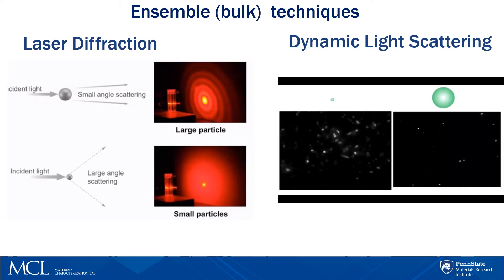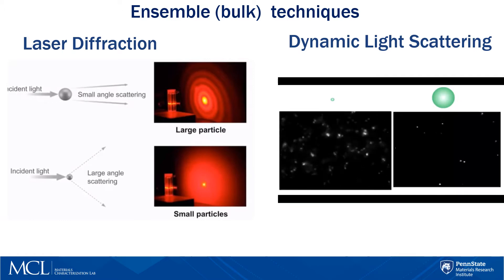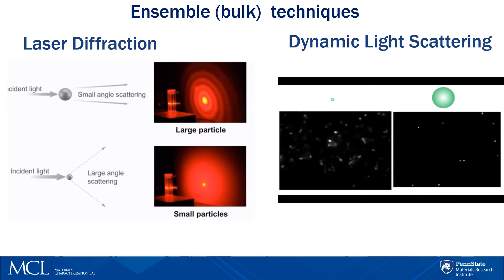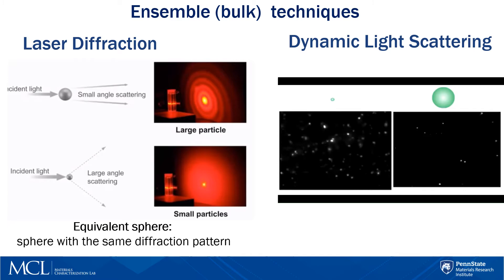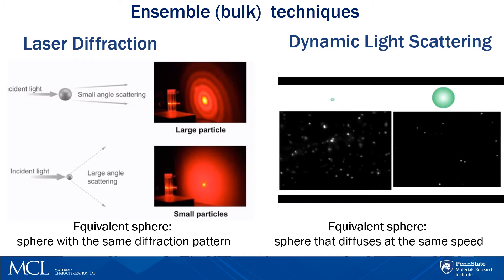Laser diffraction and dynamic light scattering are both ensemble techniques where we measure a combined or bulk signal from all particles. Laser diffraction is based on the measurement of diffracted angles — small particles diffract at large angles and large particles diffract at low angles. In dynamic light scattering we measure the diffusion coefficient, where small particles diffuse faster and large particles diffuse slower. To simplify the measurement process we use the concept of equivalent spheres, where particle size is defined by the diameter of an equivalent sphere which has the same property as the actual particle. For laser diffraction, diameter is defined as the diameter of a sphere that creates the same diffraction pattern as the particle of interest. For dynamic light scattering, it is the diameter of a sphere that diffuses at the same speed as the particle being measured.